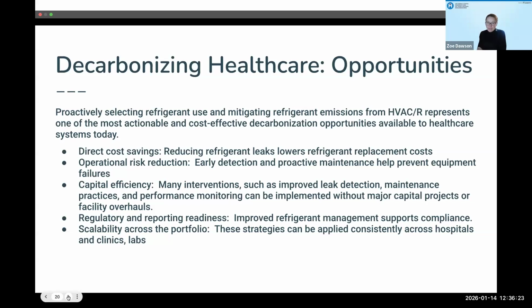Equally, let's look at proactive maintenance of refrigerant charge. What happens when you address and fix those leaks and support the performance of your equipment? You help reduce operational failure, reduce operational expenditure, and improve the efficiency and performance of that equipment. Generally, focusing on maintenance also helps reduce capital expenditures that might otherwise occur, because you're extending the life of your assets, reducing downtime, and potentially offsetting a necessary replacement.